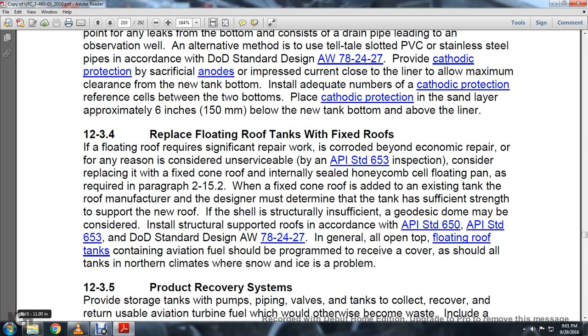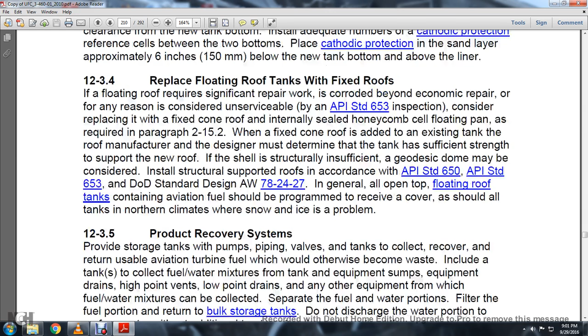The manufacturer and the designer must determine that the tank has sufficient strength to support the new roof. If the shell is structurally insufficient, a geodesic dome may be considered. Install the supported roofs in accordance with API Standard 650 and API Standard 653, and Department of Defense Standard Design AW78 2427. In general, all open floating roof tanks containing aviation fuel should be provided with a cover, as should tanks in northern climates where snow and ice is a problem.